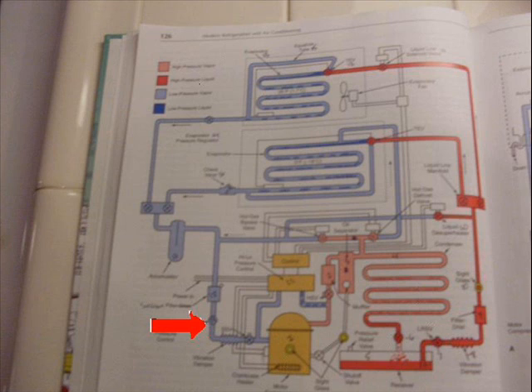So the compressor pressure regulator valve, or whatever they call its job, is to make sure the compressor sees a constant happy gas pressure, which enhances efficiency of the system. Now, you're going to wonder, what difference does that make? Now, we have to go back and add on additional parts, and you'll understand why the CPR valve is so important.